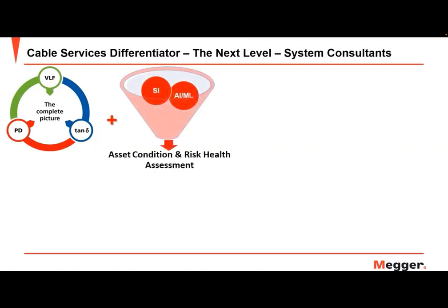We then talked about risk and health assessment, which is what we're getting into now, and asset condition. So what does the structure information look like? We can actually look at leaking bushings at transformers and report them, as I mentioned before. If the arrester is in place, fine. If it's not there, then maybe it should be put in there.